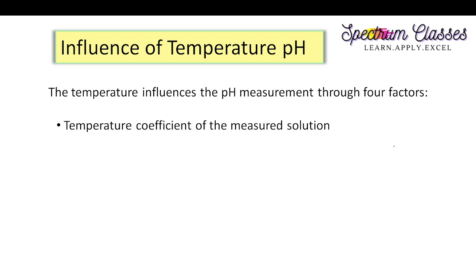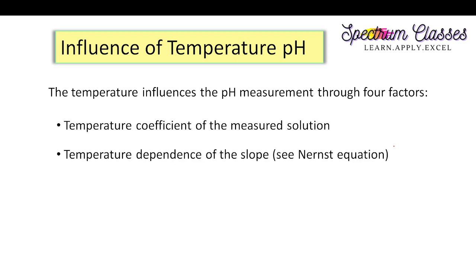pH measurement is affected by temperature in four different ways: first, the temperature coefficient of the measured solution; second, the temperature dependence of the slope according to the Nernst equation; third, the position of the isothermal intersection — which I will discuss while covering calibration of the pH meter.